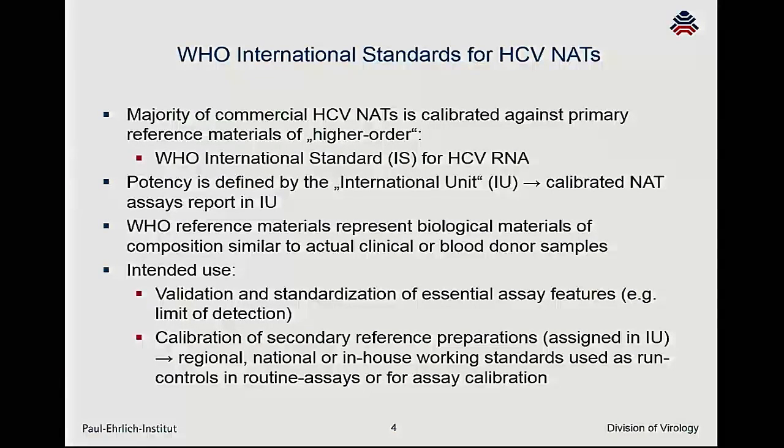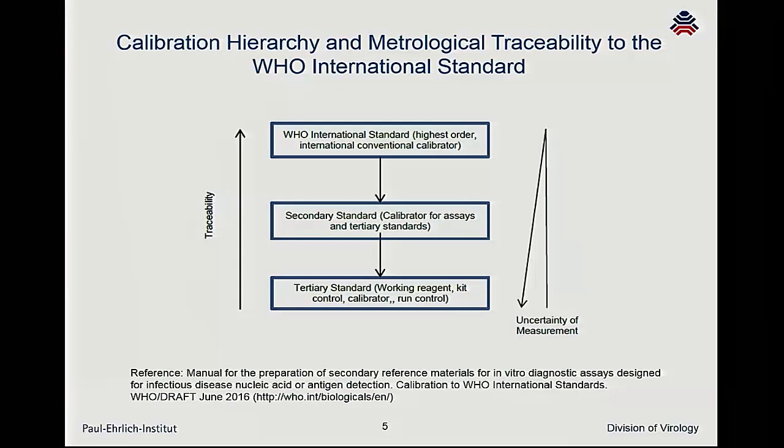On the next slide, I just want to show you the calibration hierarchy and metrological traceability to the WHO international standard. As you can see, the WHO international standard has the highest traceability, followed by the secondary standards and the tertiary standards. The uncertainty of measurement changes by using secondary standard or tertiary standard material.